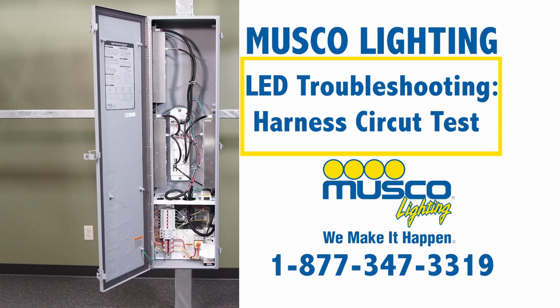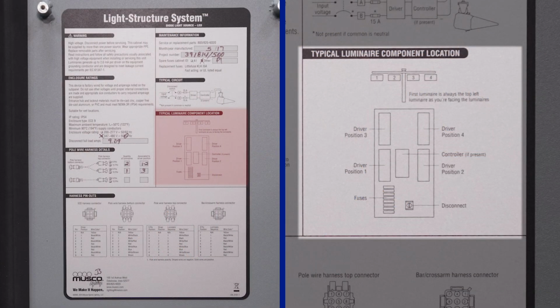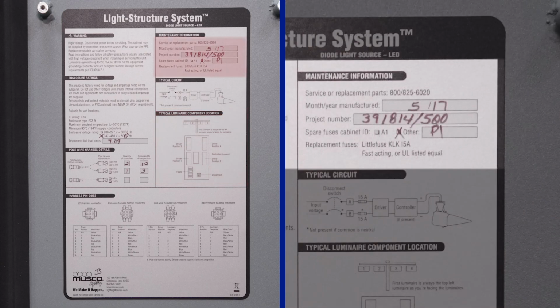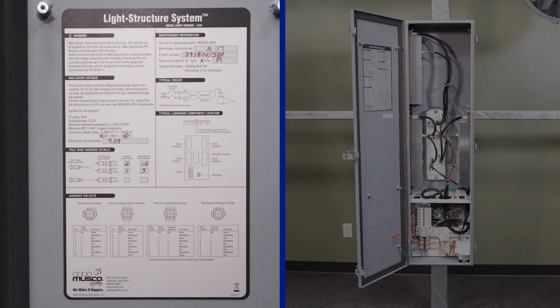When troubleshooting MUSCO lights, first verify the outage and pole location. Then find the project number, pole ID, and fixtures powered from the pole, all of which will be located on the label in the enclosure.